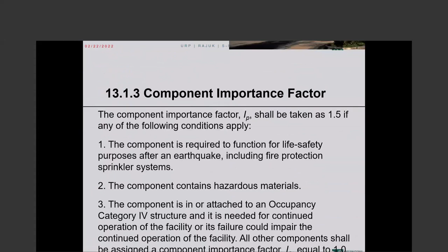The factor shall be taken as 1.5 if any of the following conditions apply: one, the component is required to function for fire safety purposes after an earthquake, including fire protection sprinkler systems - pretty clear cut. Two, the component contains hazardous materials which, when released, can do harm to the public. And three, the component is in or attached to an occupancy category 4 structure - those are essential facilities and hazardous facilities - and is needed for continued operation of the facility, or its failure could impair the continued operation of the facility.